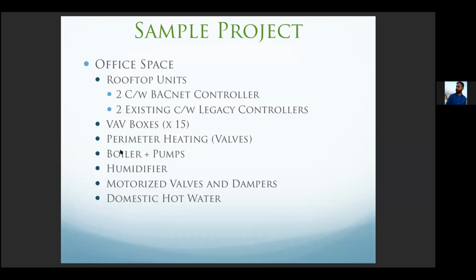Motorized valves and dampers. So now again, we talked about how to control these. It's an analog or a binary output that you're sending to the actuator of the valve or the damper, depending on what it is. So we need to account for that. Sometimes these dampers are massive. So what may happen is the manufacturer is going to break it down into little pieces and ship it to site. Now, in that scenario, you may have more than one actuator per damper, and you need to account for those extra points as well.